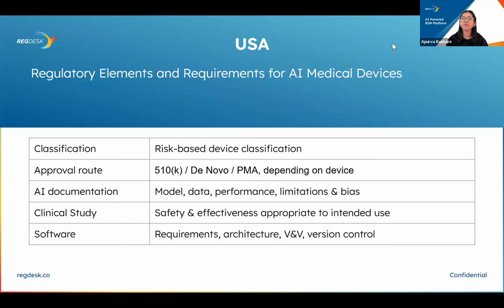Moving on to the next slide, we have some regulatory elements and requirements for AI medical devices. As you know, the classification is risk-based. Pre-market authorization for an AI device software function with a PCCP can be established through the PMA pathway, or the 510(k) or de novo pathway as appropriate, as a PCCP must be reviewed and established as part of the marketing authorization. Also, just a note: on January 6th of 2025, the FDA published a draft guidance on AI-enabled device software functions, which covers lifecycle management and marketing submission recommendations. I have attached links to all the guidance documents I have referred to in the last slide as references, so you can click and take a look at them.